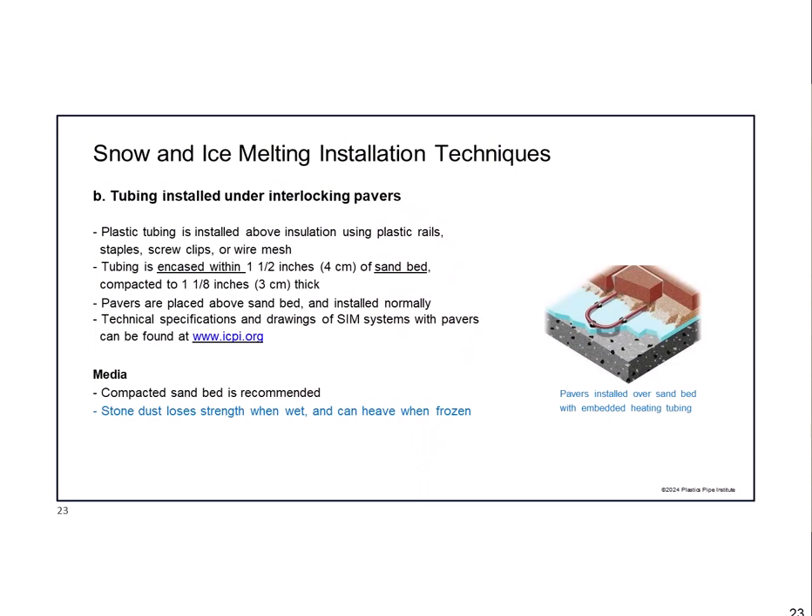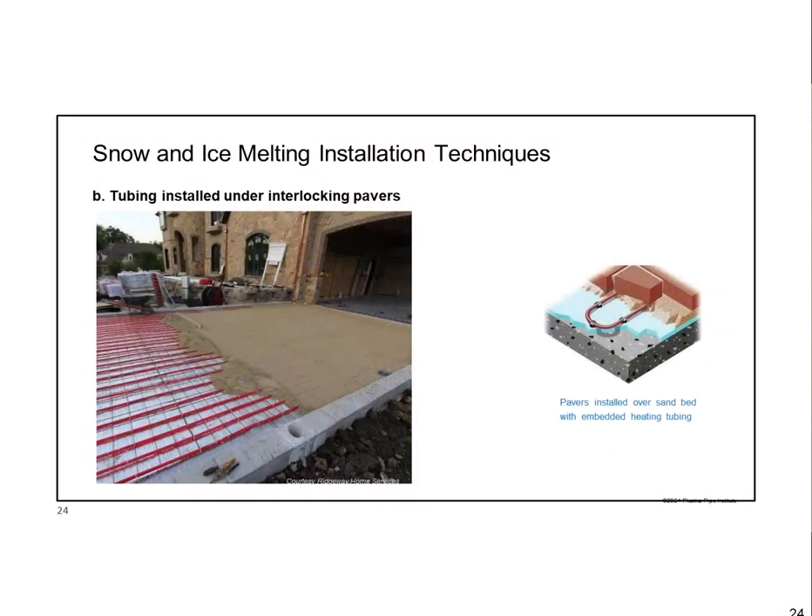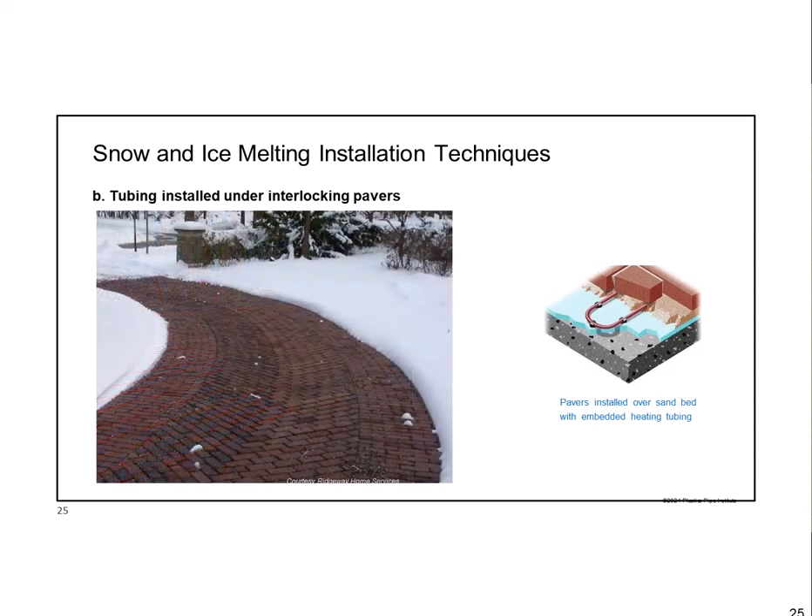For paving stones, it's pretty simple. Again, you put an insulation base down first, then you can staple or clip the tubing to the insulation base. A thin layer of compacted sand goes around the tubing—that sand is your thermal mass conducting the heat. You want it as dense and compacted as possible since air voids are bad for heat transfer. The paving stone installers put sand down anyway, so this is straightforward. ICPI.org—the Interlocking Concrete Pavement Institute—has good cutaway drawings showing how to build a snowmelt system with paving stones. Here's a nice picture of one in progress with tight tube spacing, and here's one that's working—you always see a nice crisp clear edge at the heated area boundary.